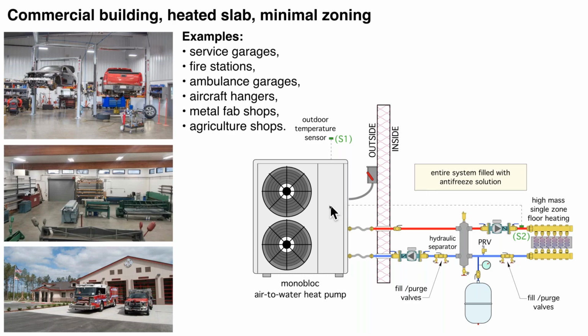It can be a very simple system where an air-to-water heat pump, in this case a monoblock, goes through a hydraulic separator and then out to floor heating. The reason a hydraulic separator is in there is to allow constant circulation in the floor circuits, which I'd like to do in garage type facilities because it helps get rid of the cold spots right inside these large overhead doors, okay?